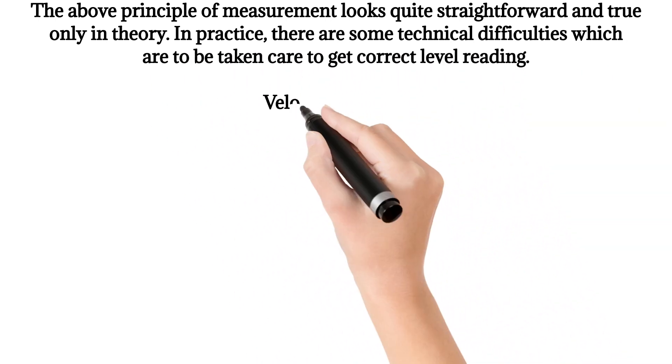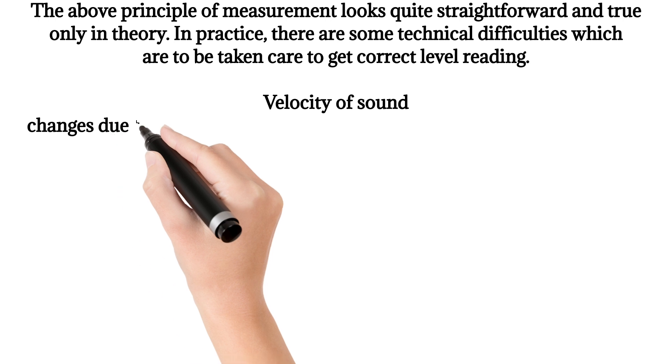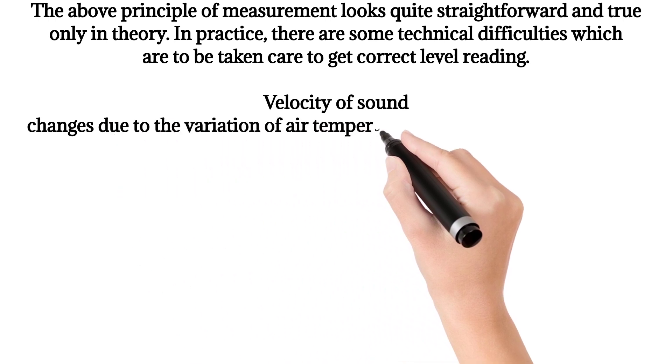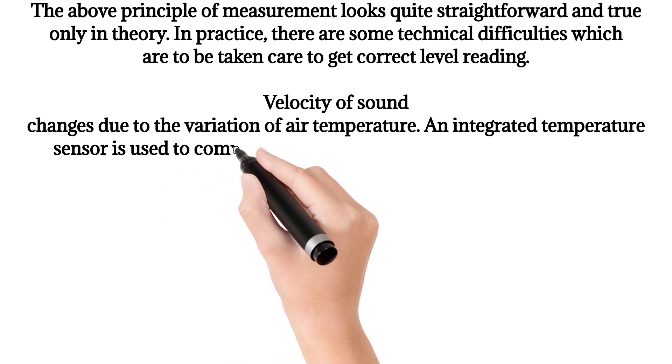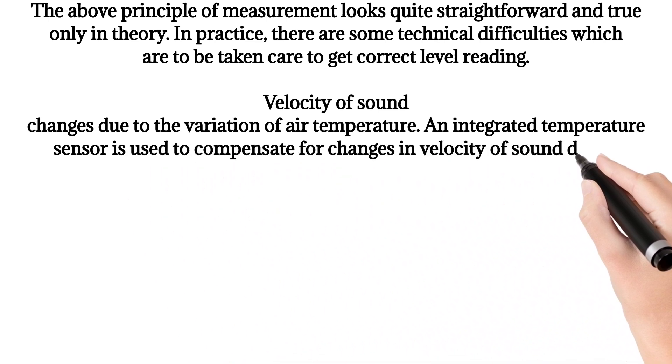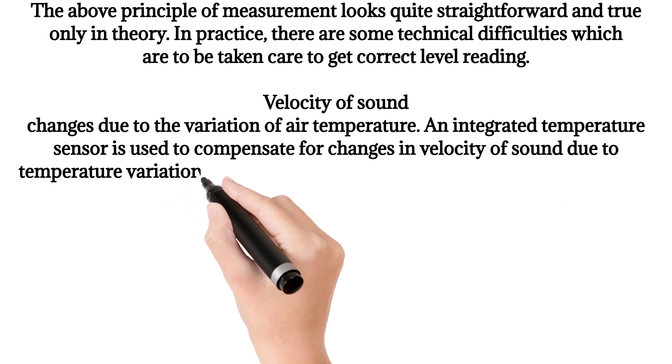Velocity of sound changes due to variation of air temperature. An integrated temperature sensor is used to compensate for changes in velocity of sound due to temperature variations.